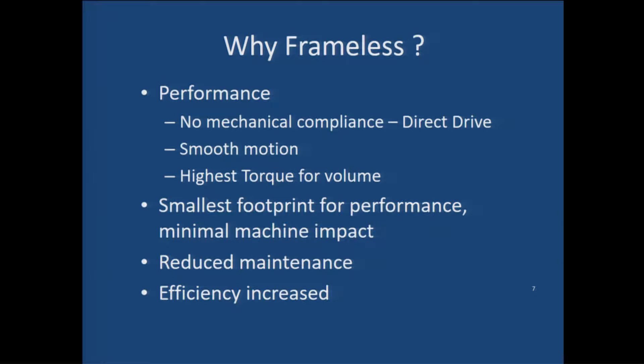We mount the stator in proximity to the rotor. Many people say they don't want to be in the motor business. On this relatively small diameter motor, there's 25 thousandths of an inch of air gap on each side — 50 thousandths total. The precision of your shaft, typically one to two thousandths TIR on existing shaft development, is well ahead of what we need. If we're in the order of three to four thousandths TIR, we're in great shape.